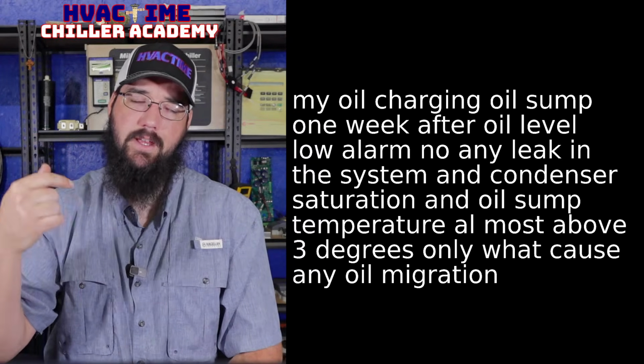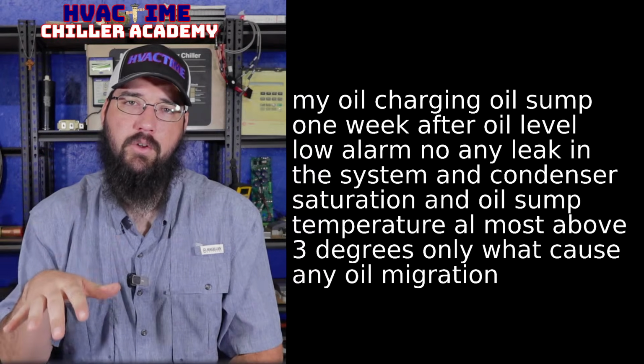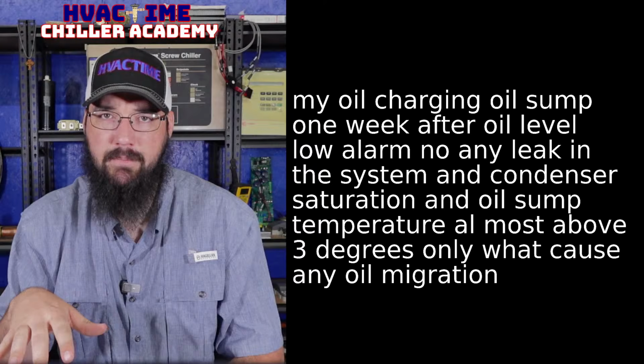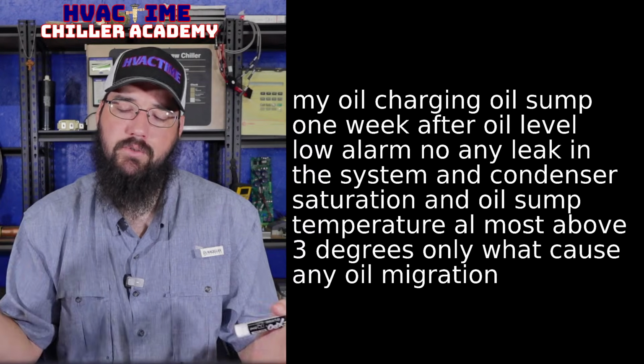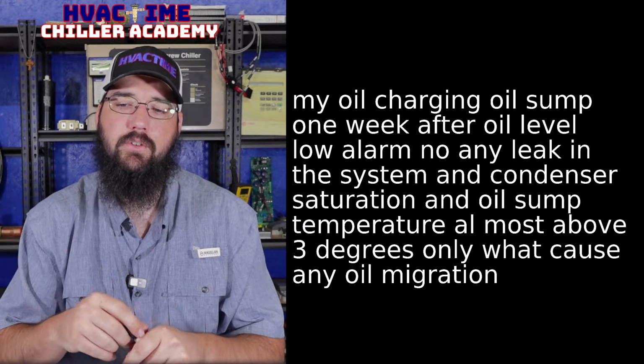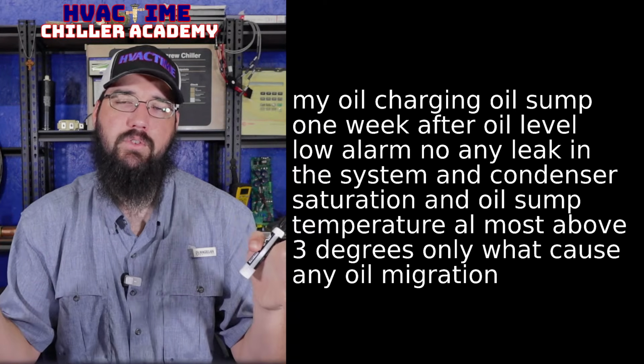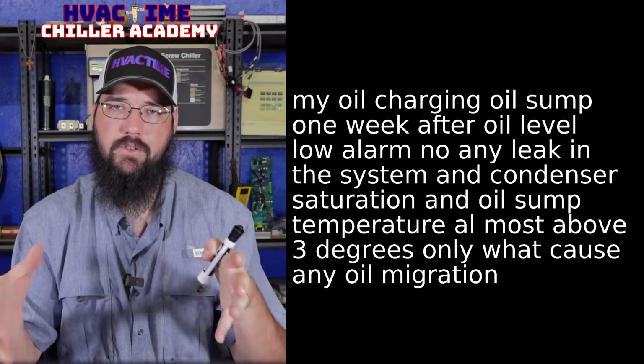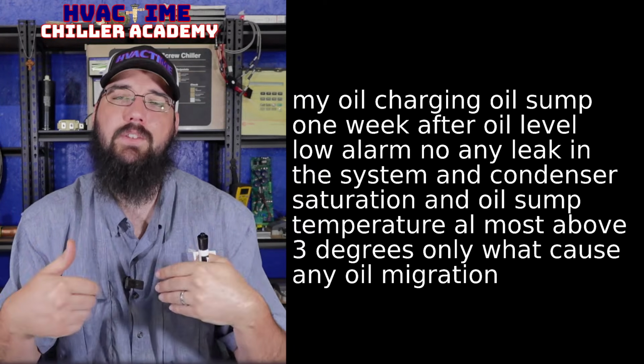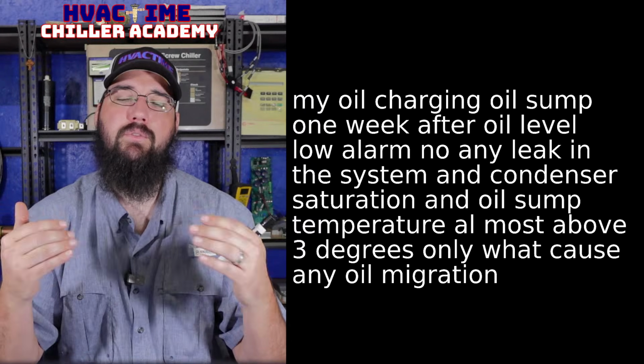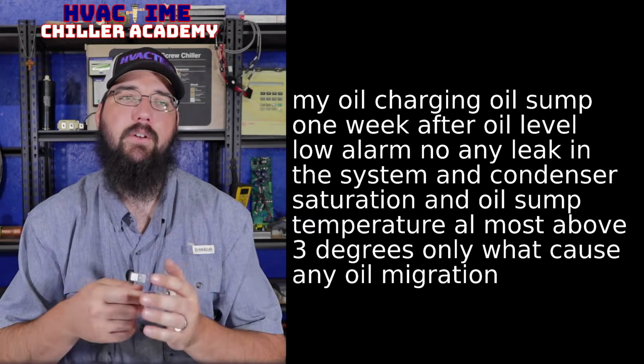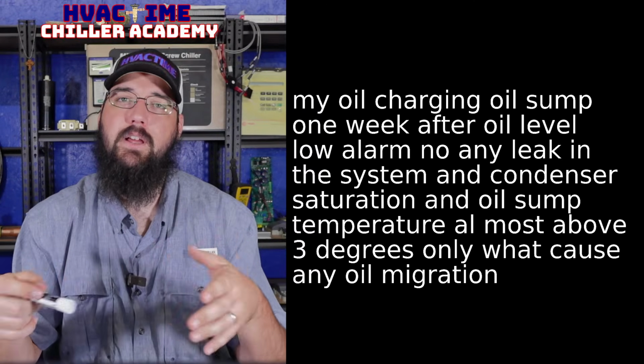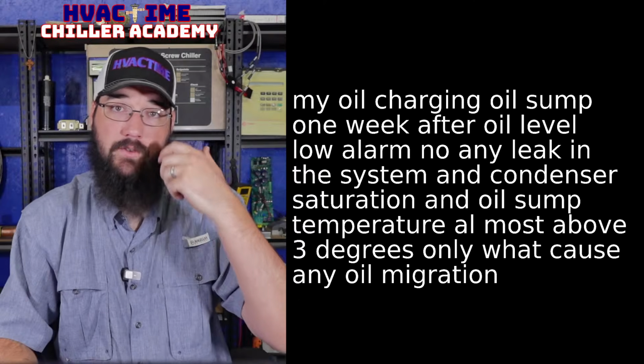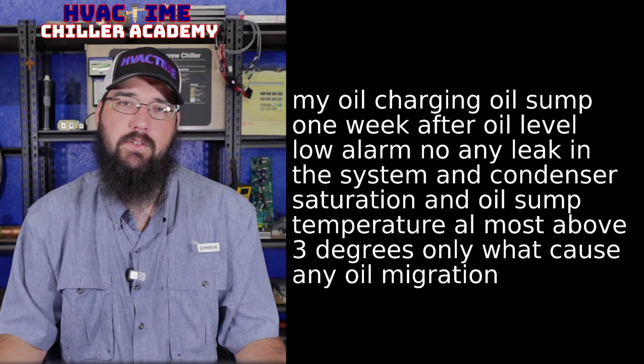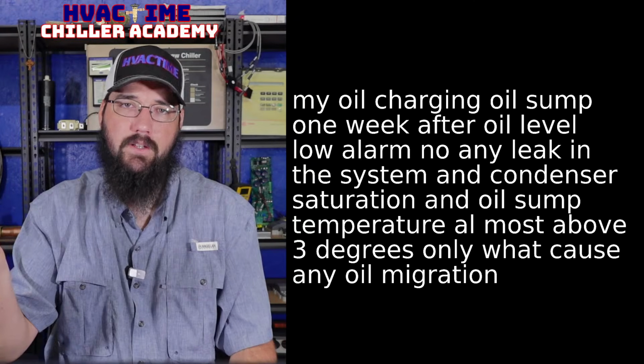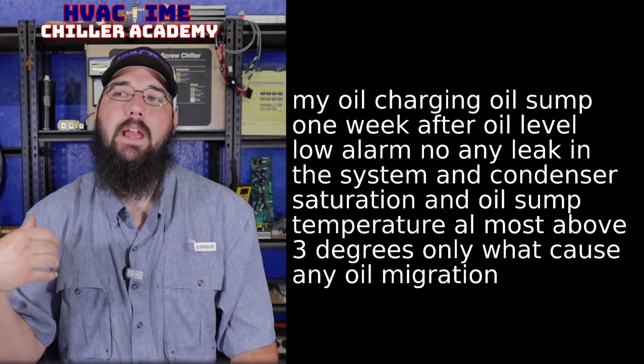because usually that oil is migrating due to an unloaded condition. Usually we're going to have a low ambient condition. We've got lower head pressure, so our DP or compression ratio is lower on the circuit at that time. So typically for those machines, when you've got these conditions lining up and we've got low refrigerant velocity moving through the heat exchanger, the evaporator, that's when we're going to start to see that oil begin to stack because it can't get carried back through the suction properly. So it is as simple as just get your velocity up, increase your DP, and you'll get that oil to return back.